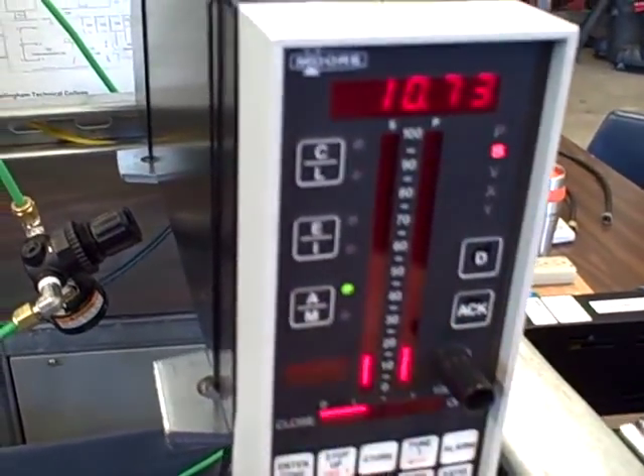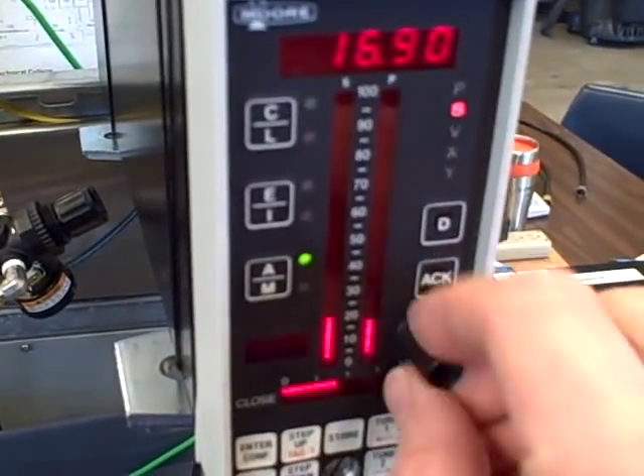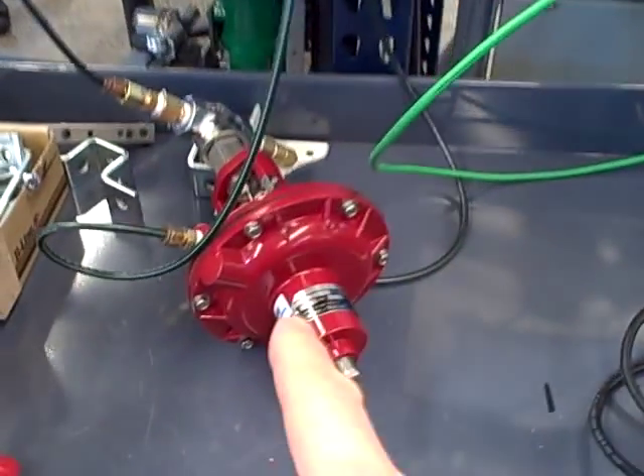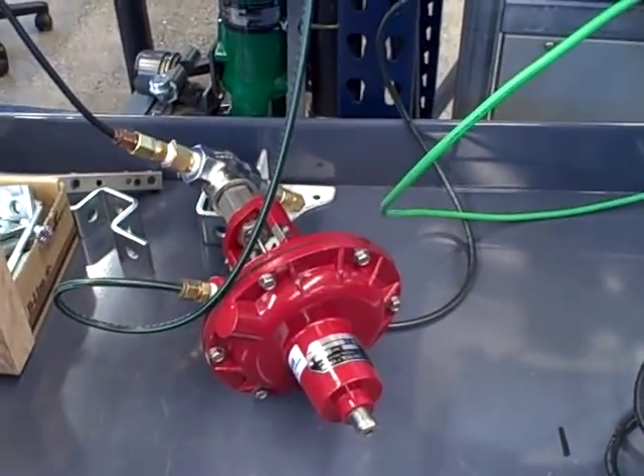The last time we tried this, it was horribly over-responsive at the bottom and under-responsive at the top. Now it's much more consistent. The only thing we did differently here is change out that control valve to an equal percentage trim.